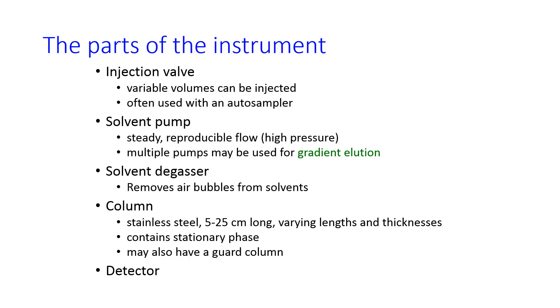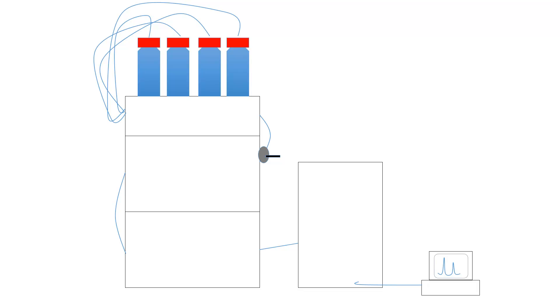What it looks like when you walk into a lab and see an HPLC is something like this, just a series of boxes. On top, you usually have the solvent bottles. They can also sit off to the side. The degasser is the next thing down, and then typically you have the pump below that. The column is below that. And so the solvent flow goes from the bottles through the degassing membranes, through the injector, and is pumped onto the column, and then finally into the detector, which can be UV, it can be a fluorescence detector, or you can use a mass spectrometer. And the signal from the detector gets read by a computer and turned into a chromatogram.